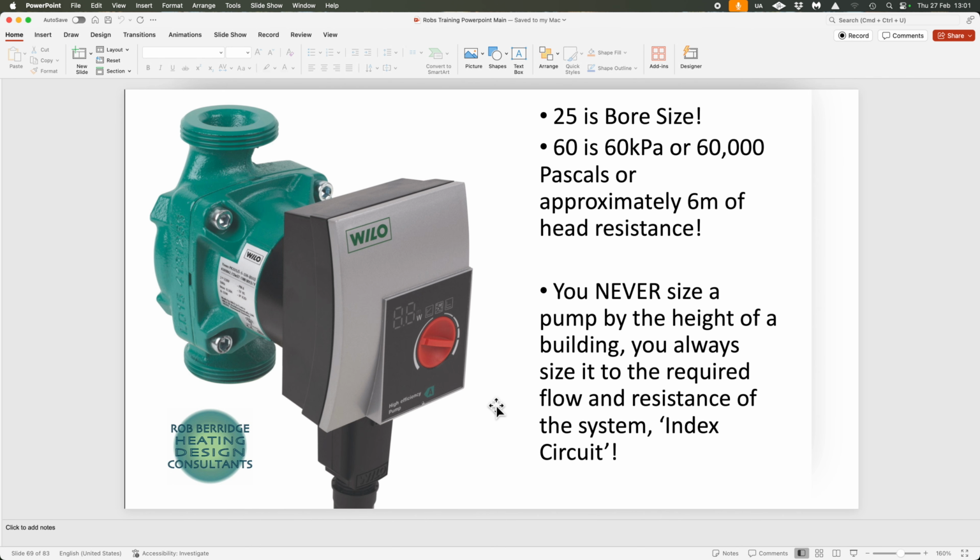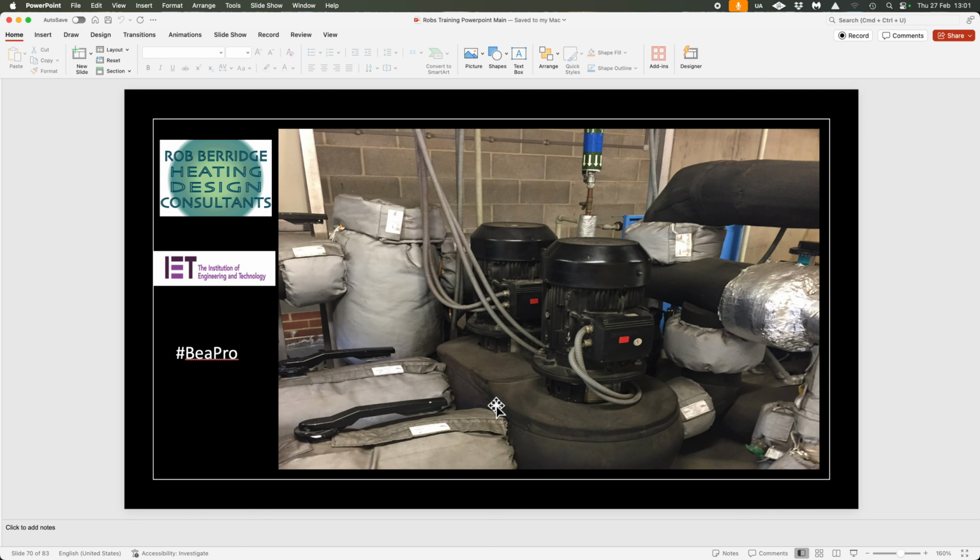And I'll show you now how, when we size a pump, the differences can actually make a big impact when we move to the next slide. So just watch this, quite interesting. This was a live commercial project that I did, and these were 2 fixed inverter pumps on this project. Now this was serving 238 flats, I think it was, up in Stevenage.